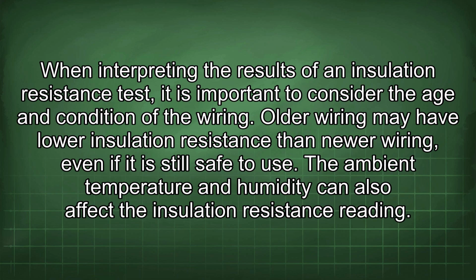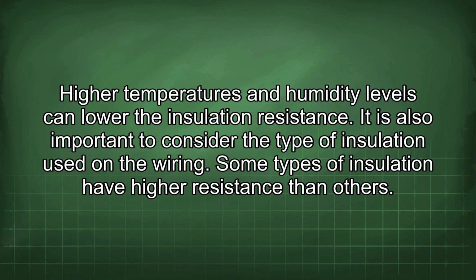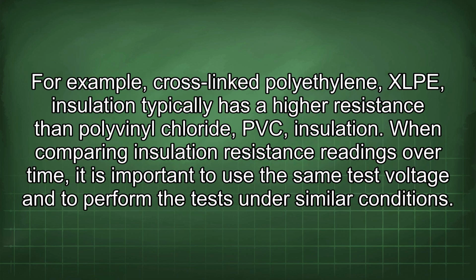Older wiring may have lower insulation resistance than newer wiring, even if it is still safe to use. The ambient temperature and humidity can also affect the insulation resistance reading. High temperatures and humidity levels can lower the insulation resistance. It is also important to consider the type of insulation used in the wiring. Some types of insulation have higher resistance than others. For example, cross-linked polyethylene (XLPE) insulation typically has a higher resistance than polyvinyl chloride (PVC) insulation.